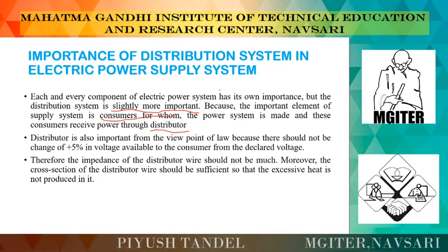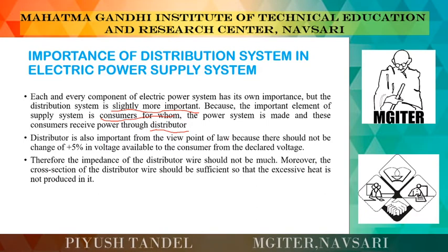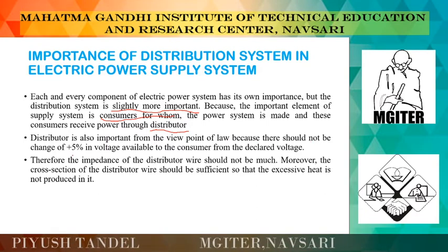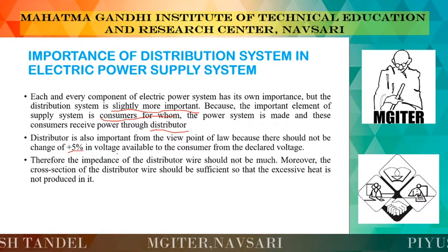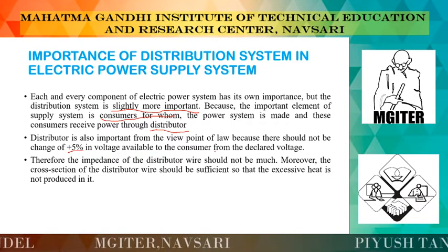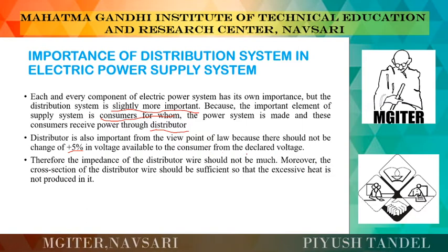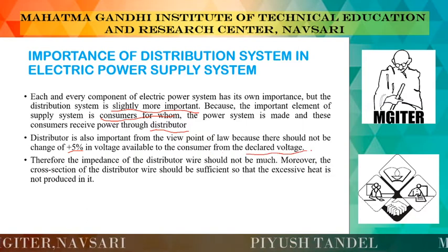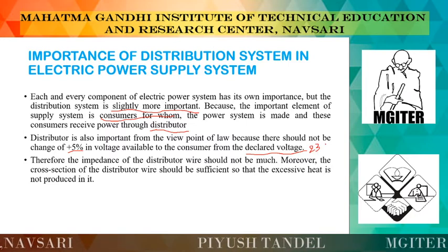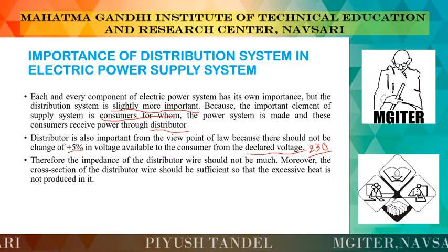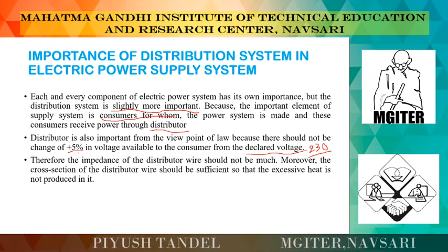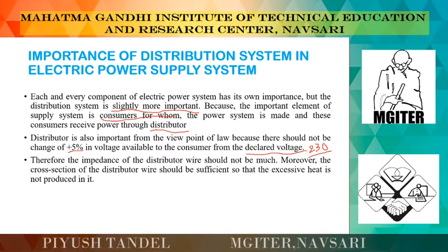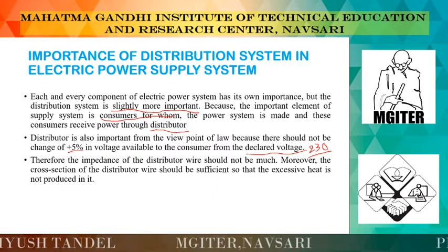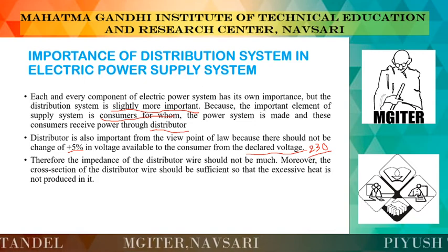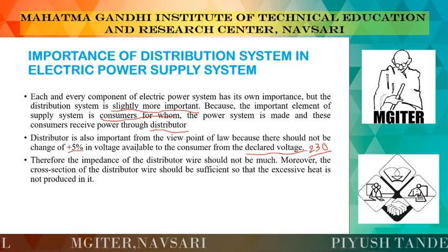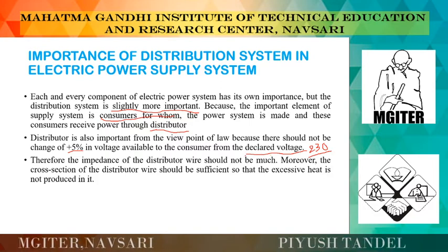Now the distributor is also important from the point of view of law, because there should not be a change of more than plus or minus 5% in voltage for the consumer from the declared voltage. So if we declare that the voltage level will be 230 volt, then we are promising that we will supply 230 volt plus or minus 5% only. Beyond that 5%, the distributor may get some amount of penalty. So the distributor has to give power at the declared voltage level.